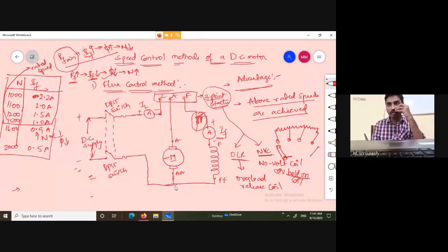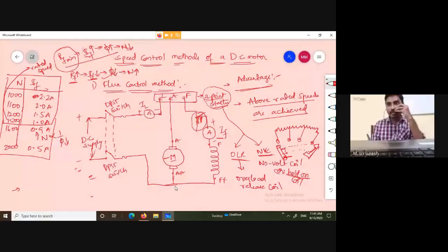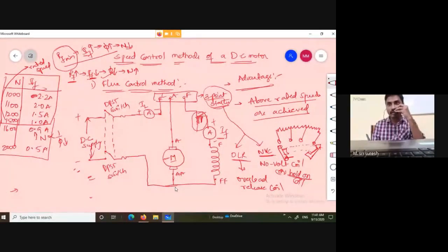Here at the on position, there is a magnet, a coil like this. Here you are having an iron piece attached. So if you are moving along these studs by moving the handle, this iron piece touches this coil. So what happens? It behaves as a magnet, so it is in a completely locked position. So this coil is called the hold on coil. It will remain until the supply is turned off. That is the purpose of this no volt coil.